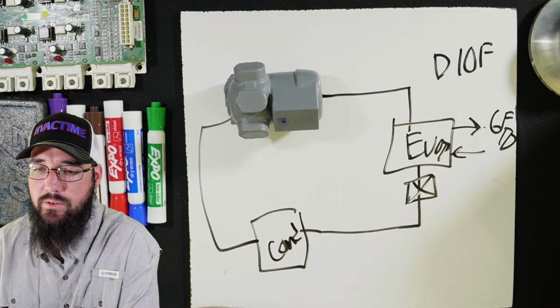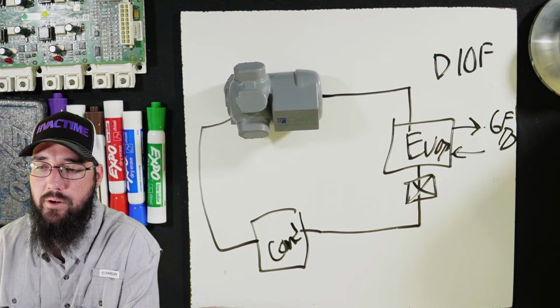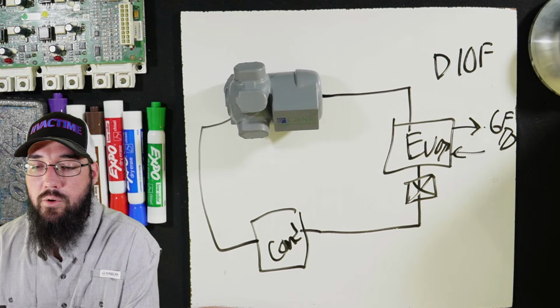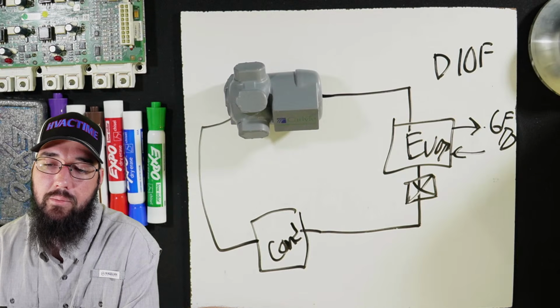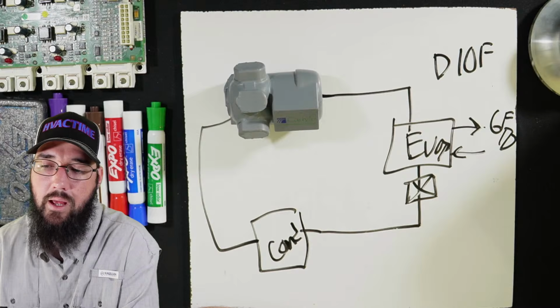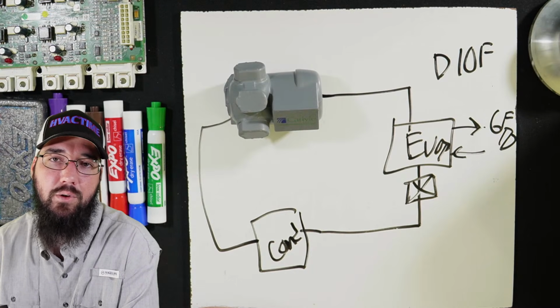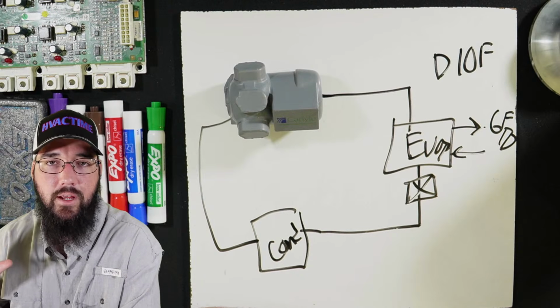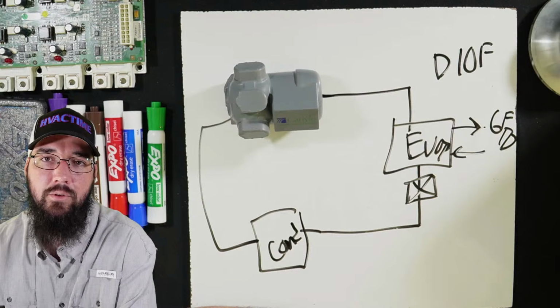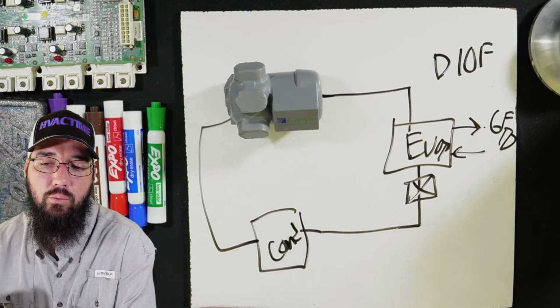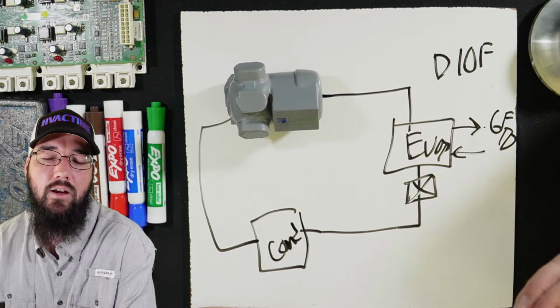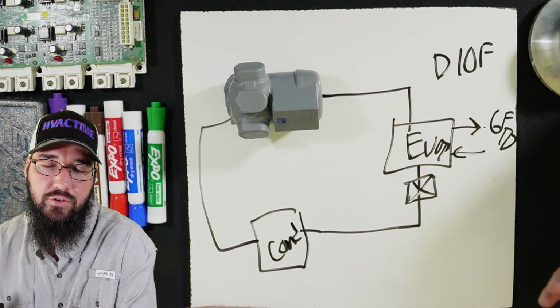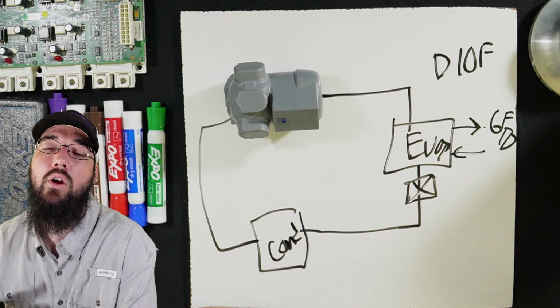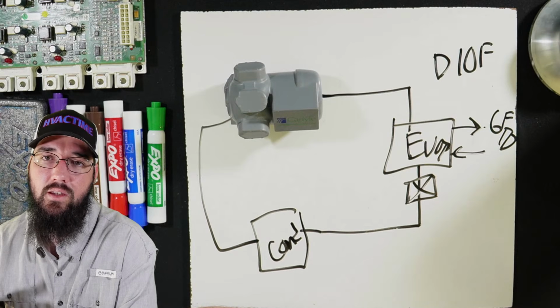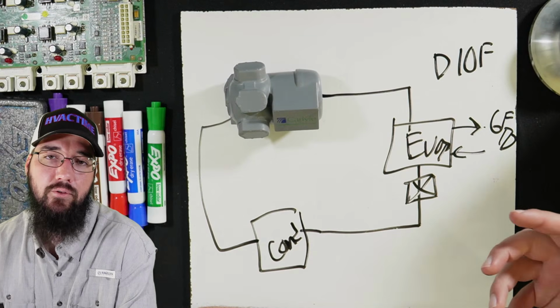Is there a difference in procedure for replacing a rear motor bearing on a YK motor with the motor in place versus motor removed on the ground? Well, I would recommend doing both bearings together. I'm not a fan of just doing the rear. If the rear has a problem, so I call that the outer, if the outer has a problem, the inner is probably going to have a problem as well, or it won't be far behind. And I would take those motor bearings very seriously, because a lot of shaft seal failures come from either misalignment or motor bearing issues, causing a lot of extra wear on the shaft seal for a YK.